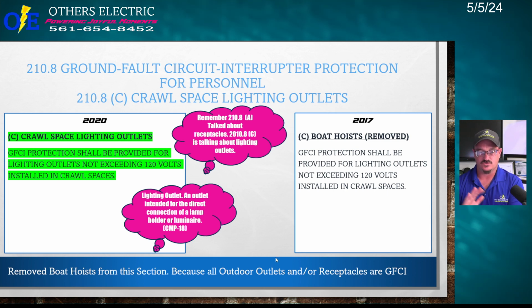Okay, so now remember, 210.8A dwelling units was talking about receptacles. So now everything else in 210.8 is going to be dealing with outlets, and you need to understand what an outlet is. Okay? Difference between a receptacle and an outlet. A receptacle is something that somebody would plug something into, like you got a 250 volt, you plug in a welder. What you're plugging into is a receptacle. The things you plug into in your house to get power, to plug in a fan or plug in a light or plug in a video game, what you're plugging into is a receptacle. An outlet is basically everything else. If you have a junction box, it's an outlet. If you have a light, you got a light. If it's something that you're going to tie a light onto, that's considered an outlet in the NEC code. If you've got a disconnect that you're going to go to an air handler unit, that disconnect is basically an outlet.